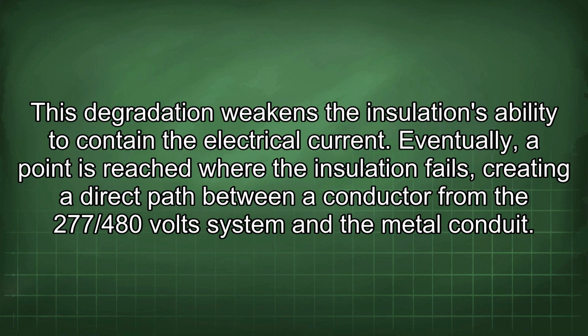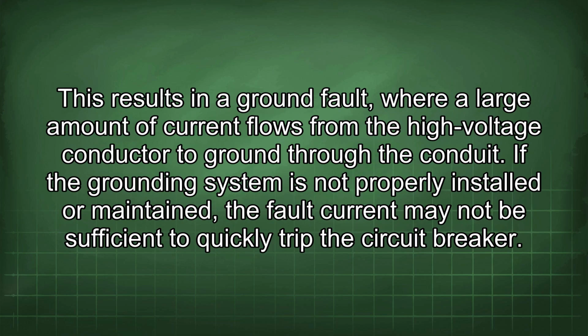Eventually, a point is reached where the insulation fails, creating a direct path between a conductor from the 277/480 volt system and a metal conduit. This results in a ground fault, where a large amount of current flows from the high-voltage conductor to ground through the conduit. If the grounding system is not properly installed or maintained, the fault current may not be sufficient to quickly trip the circuit breaker.